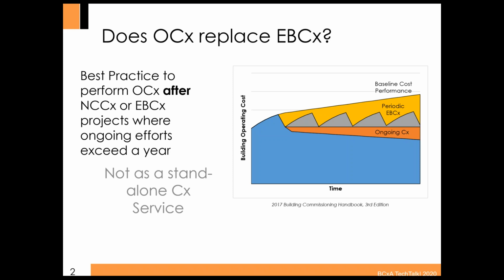The gray area, where we get that sawtooth curve, is when we start applying periodic existing building commissioning, which as a best practice happens every 3 to 5 years. We go into a building and recommission it, getting back to baseline performance, sometimes seeing slightly better performance than the initial design as we optimize to current facility requirements.